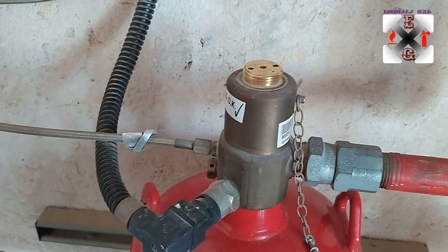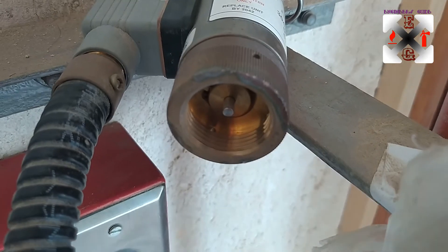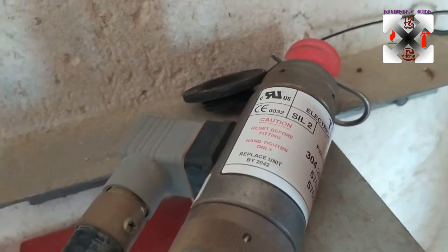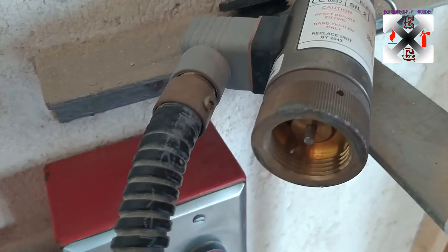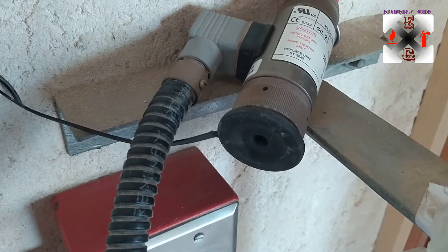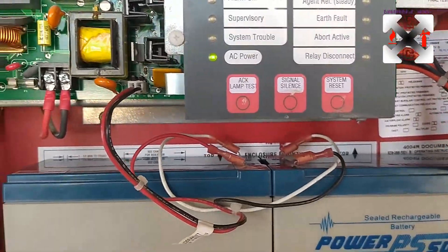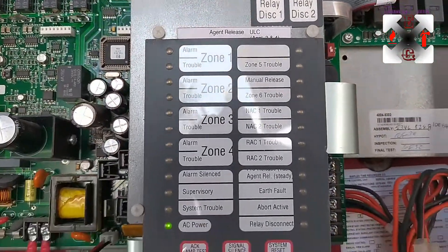This is the compressed heptafluoropropane gas compressed with nitrogen. This is the solenoid with its reset tool, and this is the cylinder head. The solenoid has been reset, so when we start to test we will show how it's going to extend. That is the reset tool attached to it — the black piece — which we use to reset it by pushing it inside and tightening it.